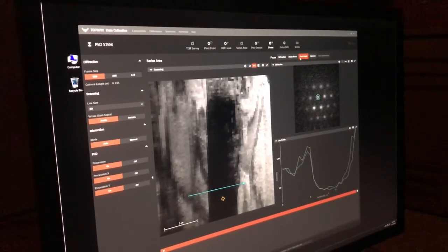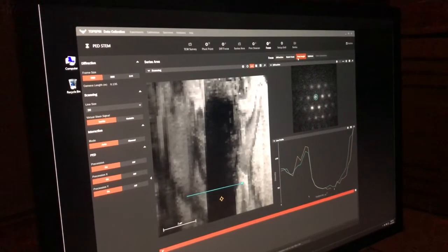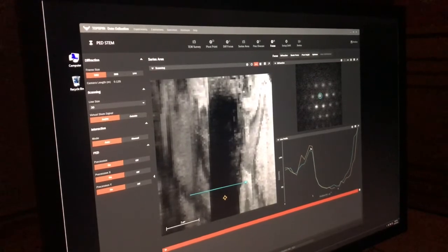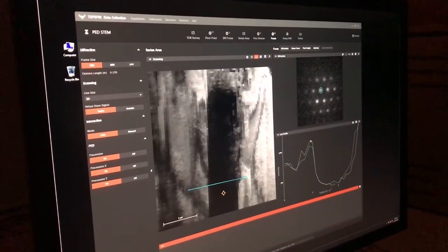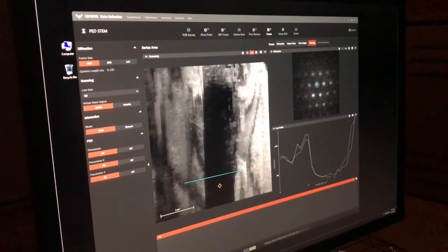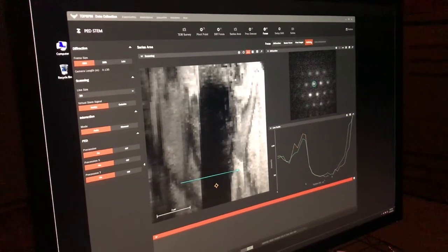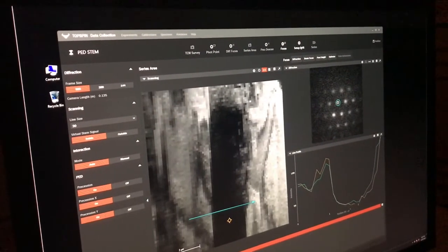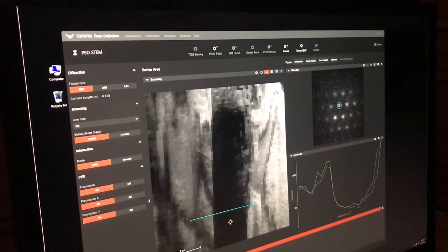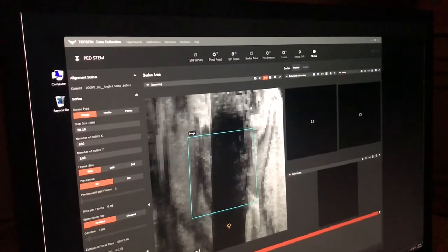Click on pivot height. You see a new profile. The new profile resembles the previous profile. This tells us the pivot height is the same as the specimen height. If you see a huge difference between these two curves, then click on optimize. In this case, we don't have to do so. We usually do not use the setup drift, so we skip step 7 and click on series to acquire the data.